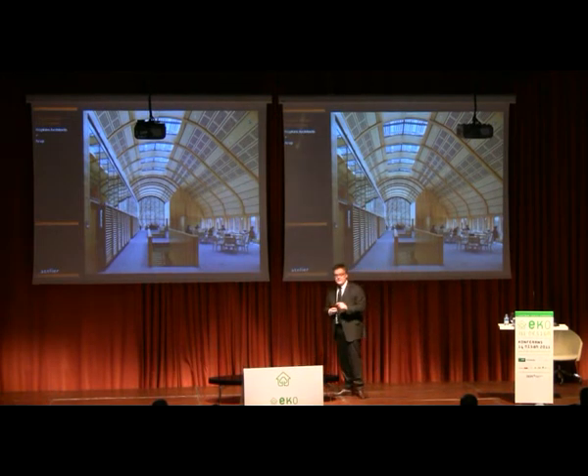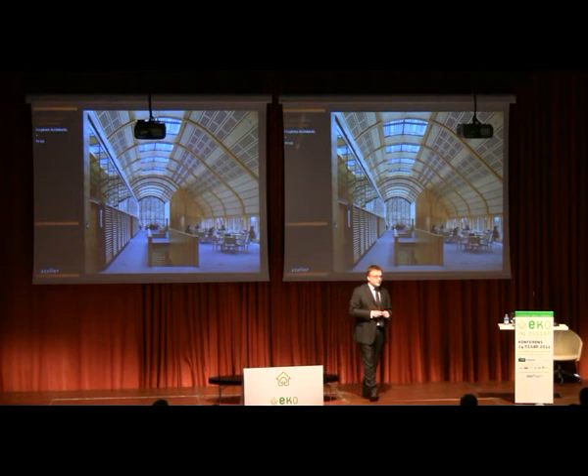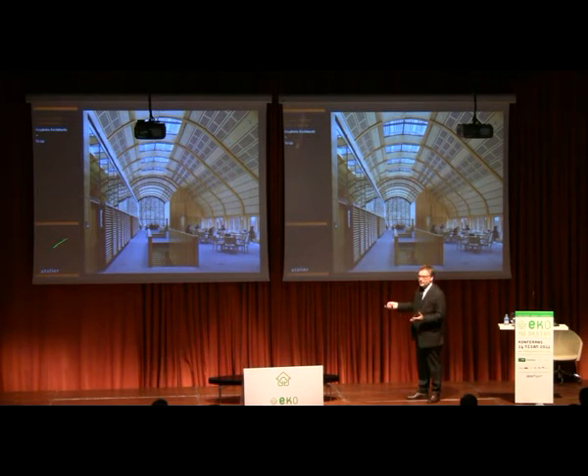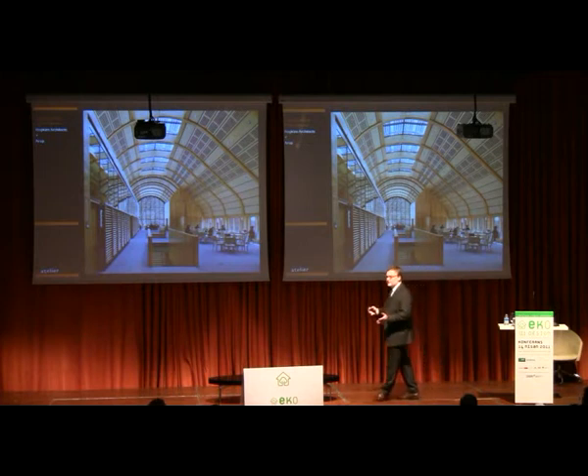Interesting problem we've got with this building now is that it's using something like 50% more energy than we predicted, and the reason is that it's so popular. This space is one of the most popular places on the Yale campus, open to all students, so every desk is occupied all day with people working. They all plug their laptops in, so plug loads are much higher than expected, and with demand control ventilation we have to ventilate more because there are more people there.